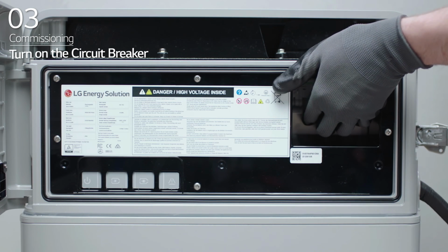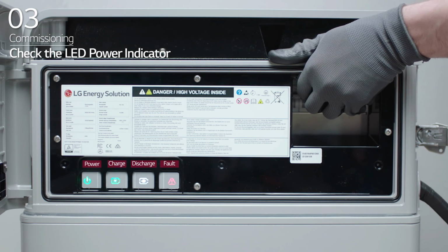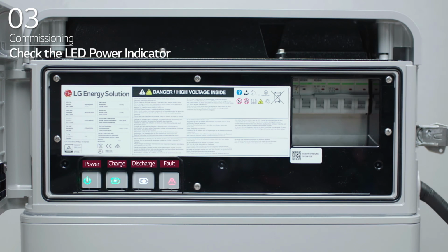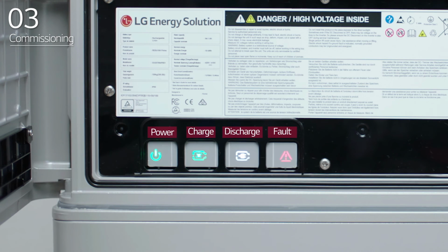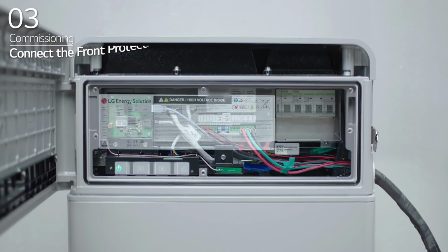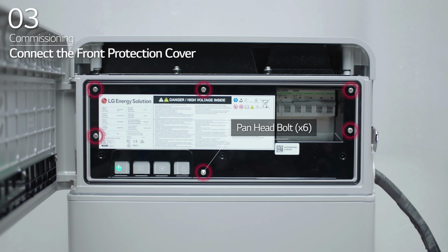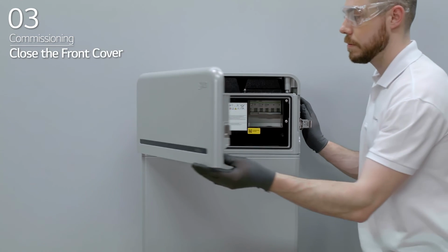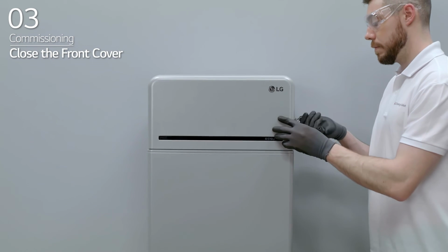Turn on the circuit breaker. Seconds after the circuit breaker is switched on, 4 LED indicators will light up. To ensure that installation has been done correctly, check that the LED power indicator is green. Connect the front protection cover using 6 M5 panhead bolts. Finally, close the front cover and turn on the inverter.